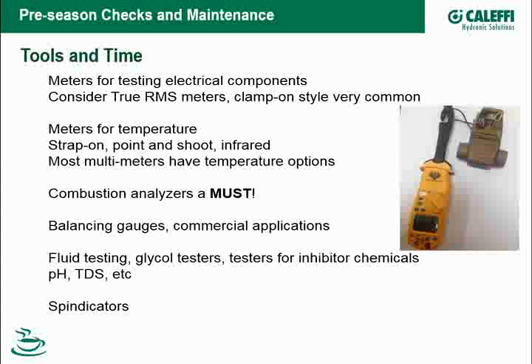So if you're working on new equipment with electronic components on it, you might want to upgrade to a new meter. There's meters for everything, and what's nice about the meters now, that little UEI that I just got, it has a lot of different attachments for it, so you don't need to have a lot of different meters because that can do a lot of different things. It can do amp readings, it can do temperature readings. It's got a little hook, like you can see there, we can just hook it right over the connection going to a zone valve and read the current draw on that. Data loggers and stuff are available for some of them.